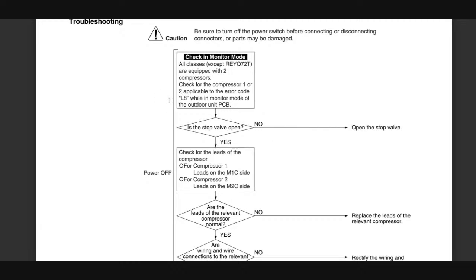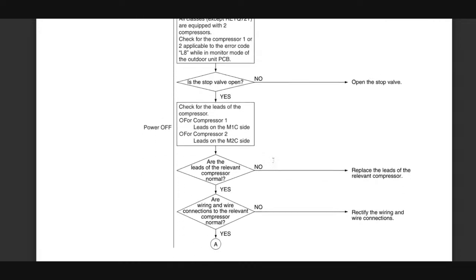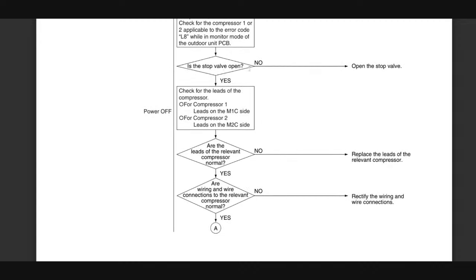All right. So with power off, check and monitor mode are equipped with 2 compressors. So let's see. Is the stop valve open? No. Yes, stop valve. This should be the solenoids that control flow. Check the leads. And now, I will preface, if you're looking at this, and let's say we didn't know what the stop valve was, there are tons of diagrams and there's tons of information in this system.